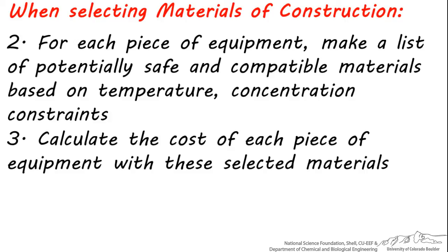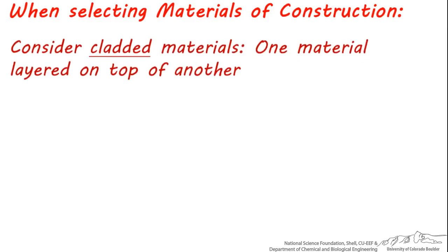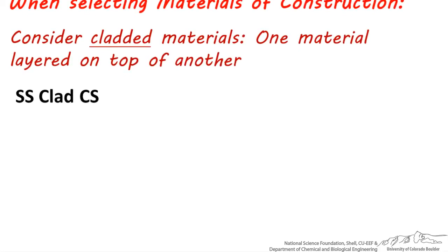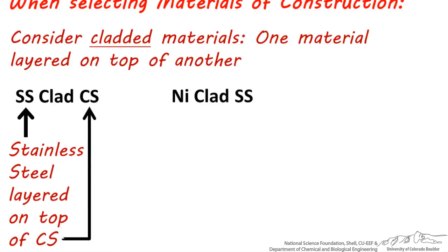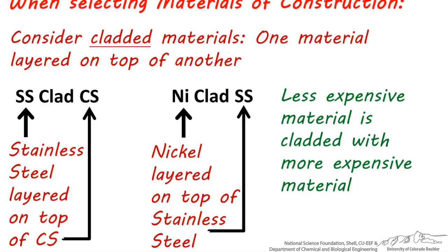Most design textbooks provide tables or software to help you calculate the cost of units with different materials of construction. If you're not sure whether it's necessary to use a more expensive material because the stream seems to be on the borderline of being reactive or damaging, consider using cladded materials. Cladding is when one material is on top of another as a protective layer. Common cladded materials in the chemical process industry include stainless clad carbon steel and nickel clad stainless steel. Notice that the less expensive material is always cladded with a more expensive layer, and choosing a cladded material can save a lot of money on initial costs compared to using a non-cladded, more expensive unit.